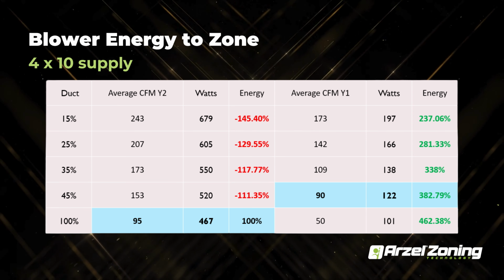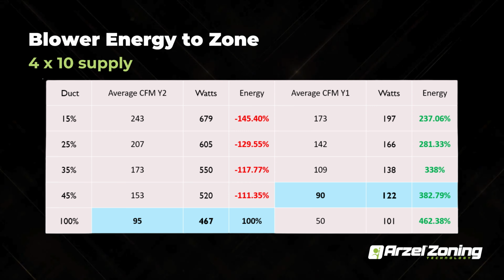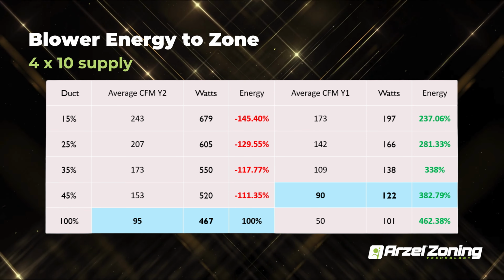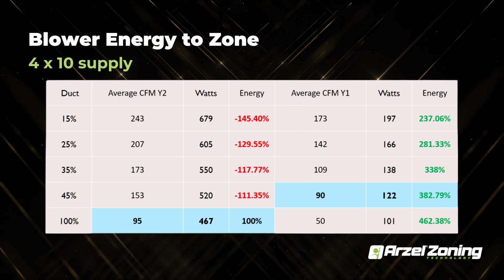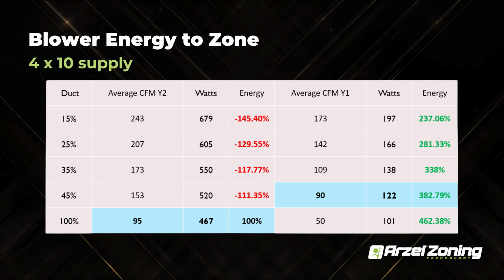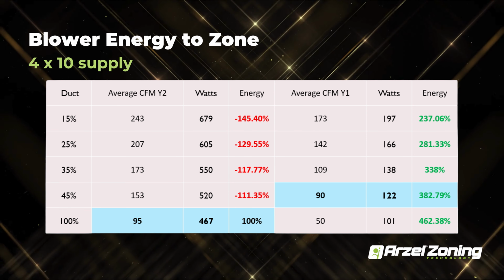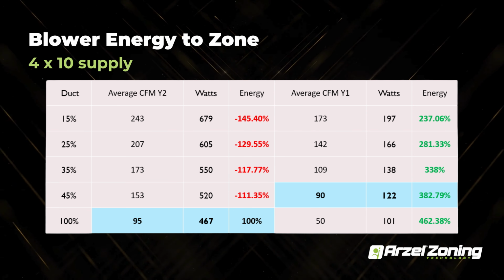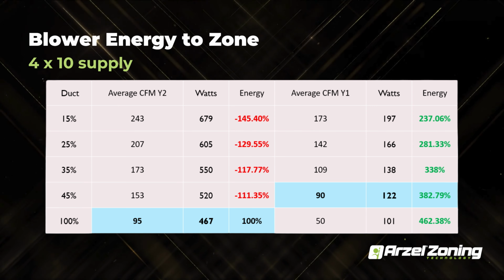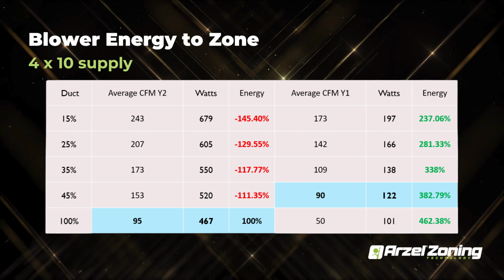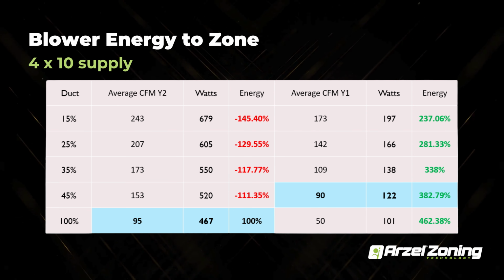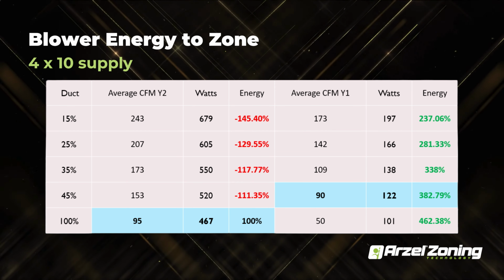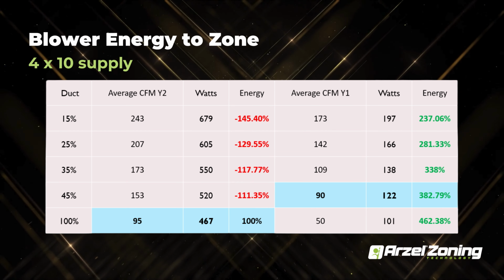It's hard to prove exactly what you're going to save, but you can save money, and these test results do show that. I mean, if you stay in that Y1 output, it's about a 300% savings. Not that you're going to run it that long. I mean, this would be if you were running a Y1 output 100% of the time. So you're not going to save that, but you can see the money savings is there. You're able to achieve the same CFM output delivery with less equipment capacity.